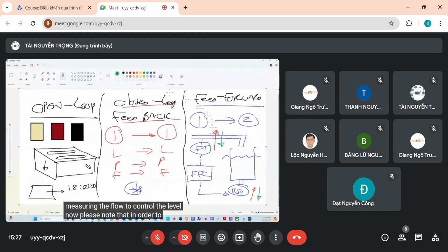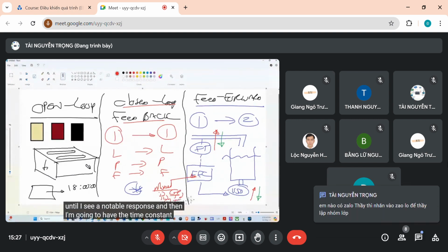Please note that in order to do this, we need a model of the process, which is going to be built into the controller. That model of the process consists of three separate aspects: the gain of the process, the dead time of the process - the time that elapses from when I change an output until I see a noticeable response - and the time constant, which is the rate of change of that process.